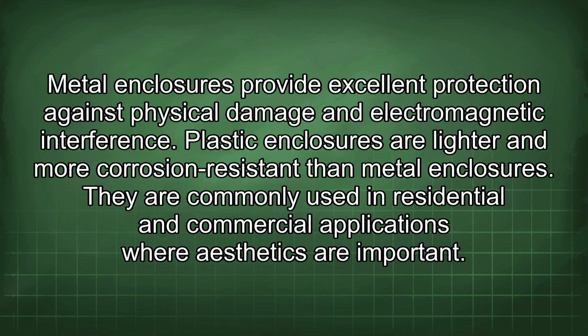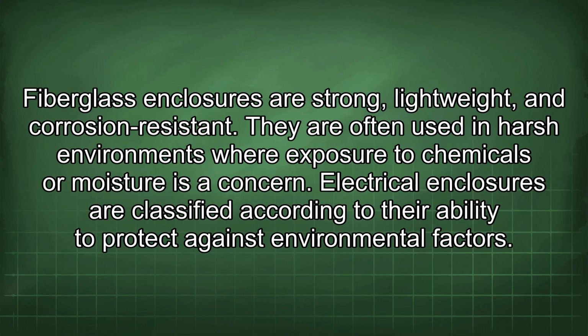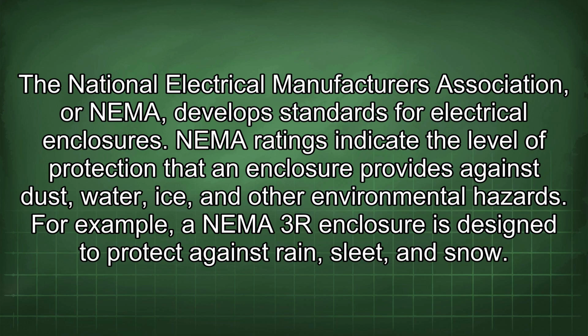They are commonly used in residential and commercial applications where aesthetics are important. Fiberglass enclosures are strong, lightweight, and corrosion resistant. They are often used in harsh environments where exposure to chemicals or moisture is a concern. Electrical enclosures are classified according to their ability to protect against environmental factors. The National Electrical Manufacturers Association, or NEMA, develops standards for electrical enclosures. NEMA ratings indicate the level of protection that an enclosure provides against dust, water, ice, and other environmental hazards.